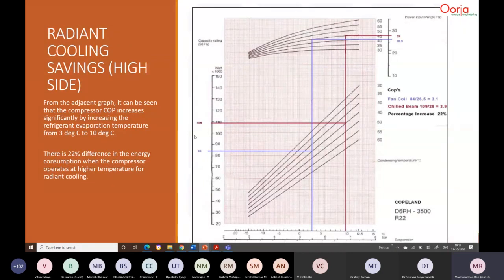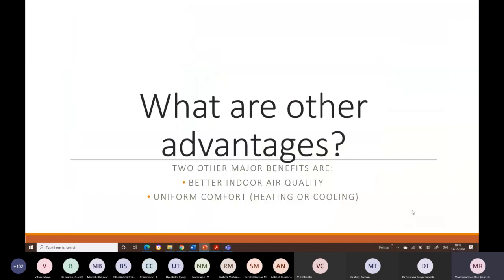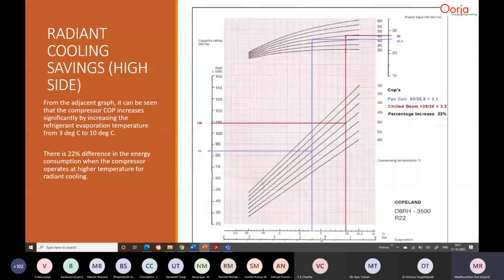So if you look at this performance graph of a Copeland compressor, what it means basically is that in the evaporator, the evaporating temperature has gone up. If the evaporating temperature has gone up, at the same condensing temperature, we will see that the output has increased from the same compressor at a slightly higher energy consumption, but the overall increase in the COP of that compressor is 22% between operating that system at 3 degrees centigrade evaporating temperature versus 10 degrees centigrade. So the higher the evaporating temperature, the lower the energy consumption.